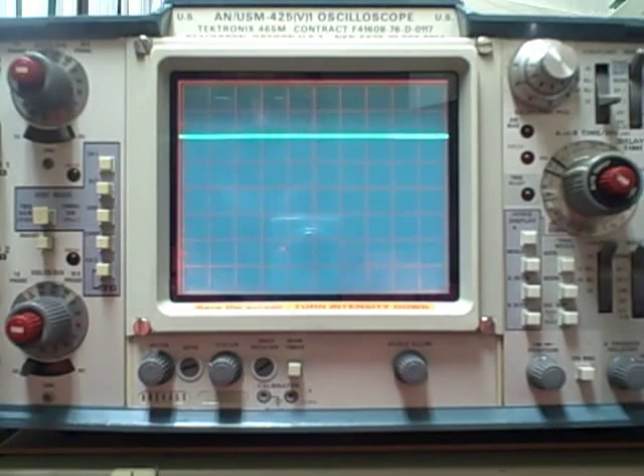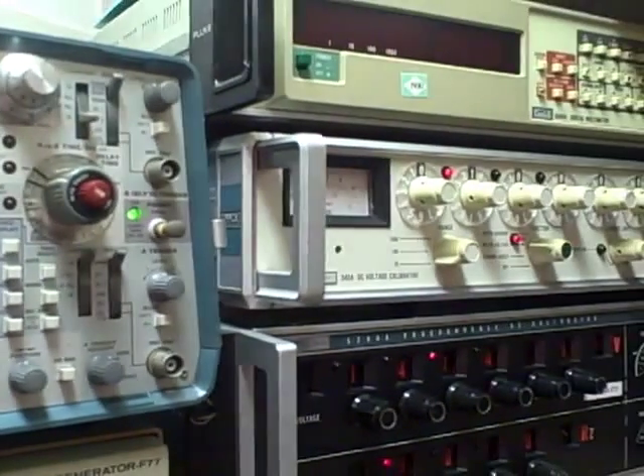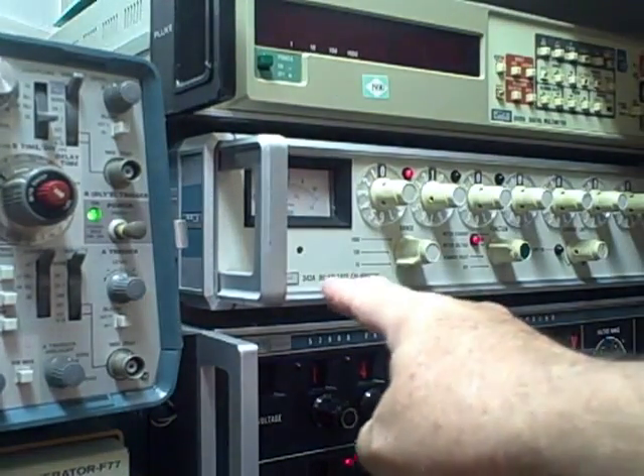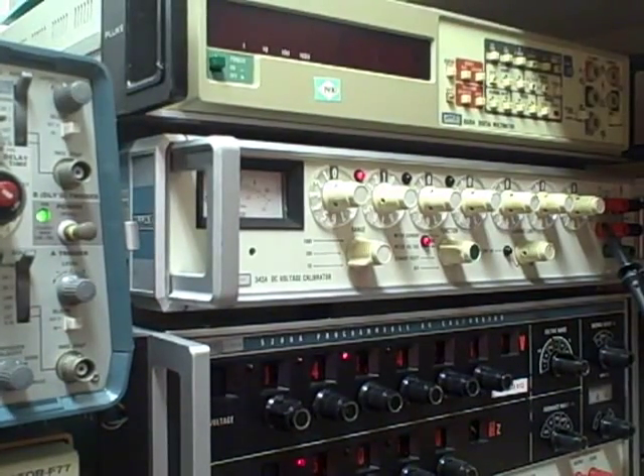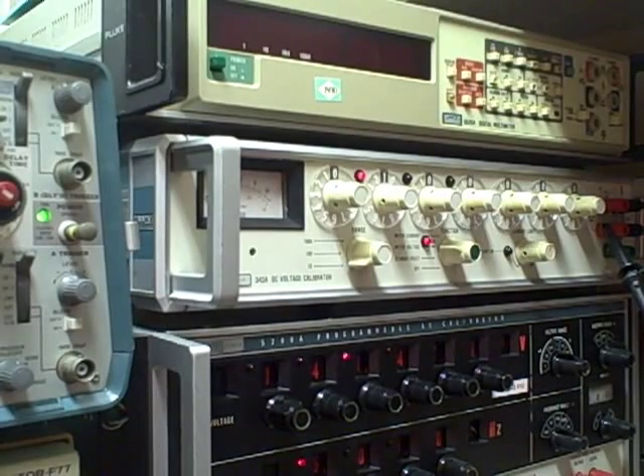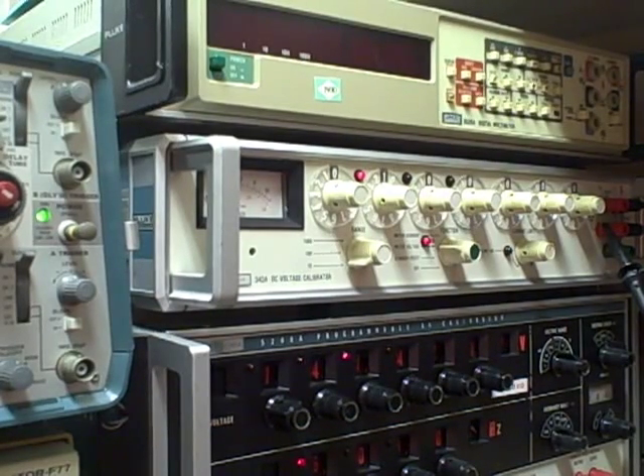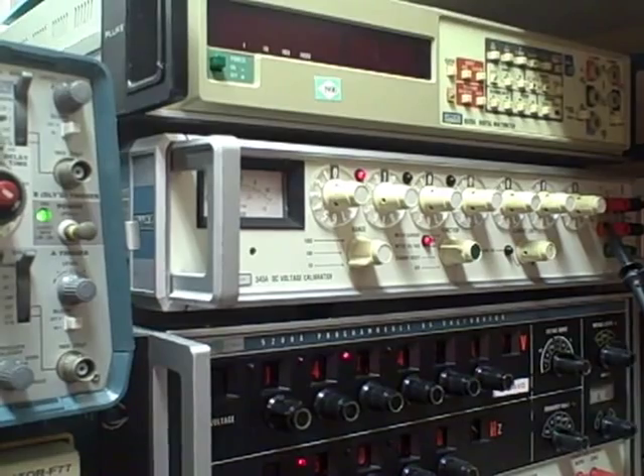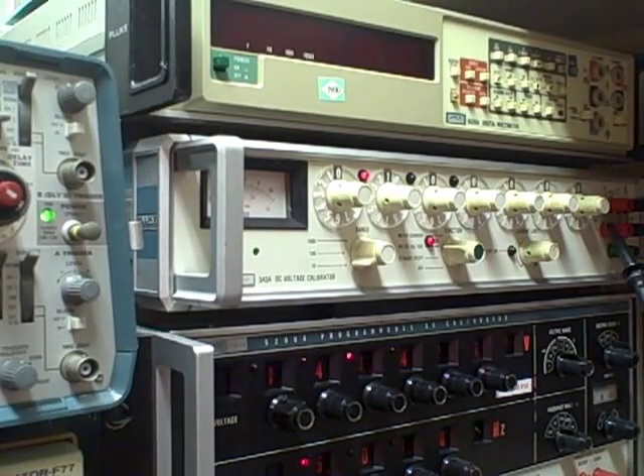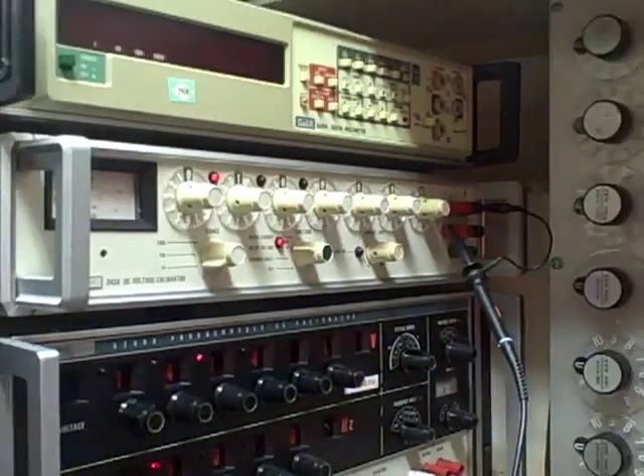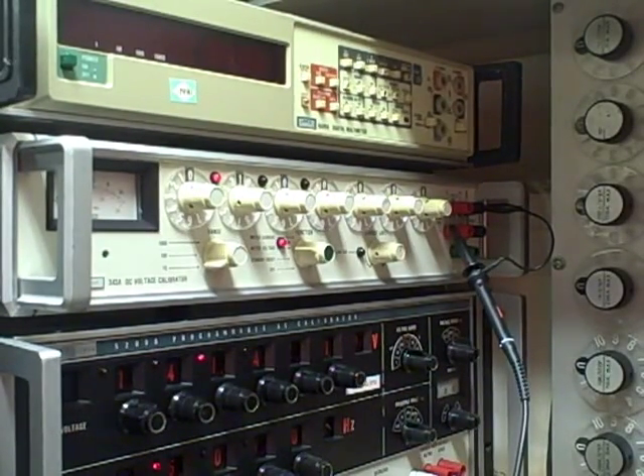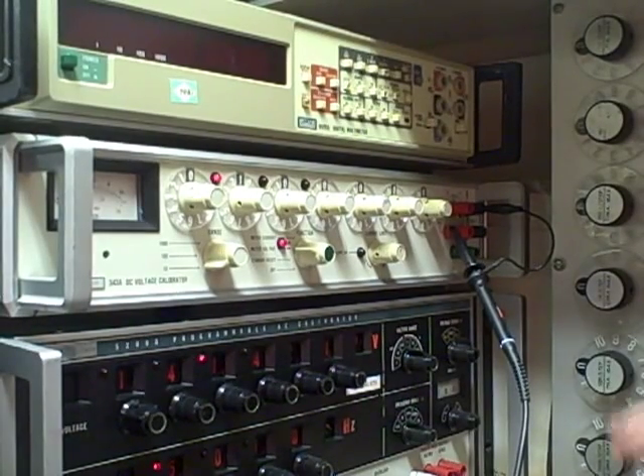Okay, so we're set up right now to film the response. I've got myself plugged into a precision DC voltage source. We're using this Fluke 343A to provide our DC voltages, and we can dial up pretty much any voltage we want from 1,000 volts down to a microvolt. So, pretty amazing unit. Because of the noise level down at the microvolt level in particular, or anything at the millivolt level, I've got the probe set right now at ×10.